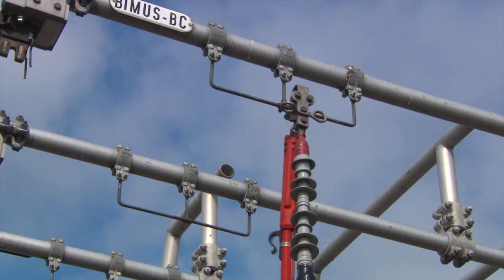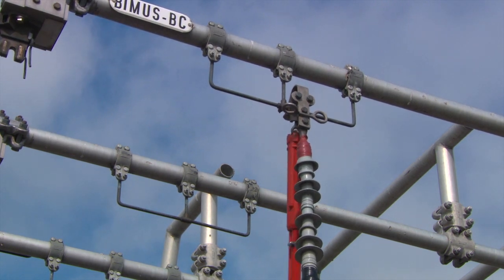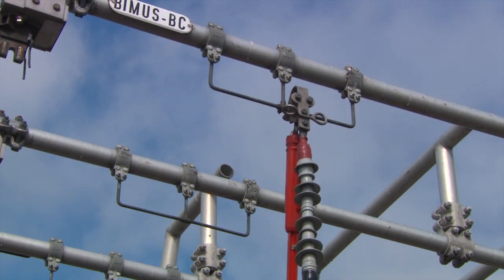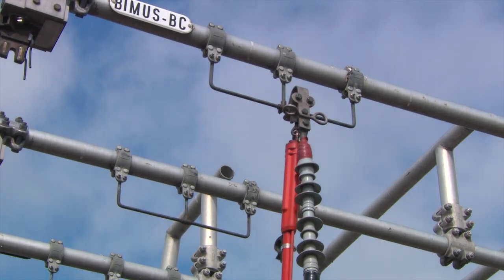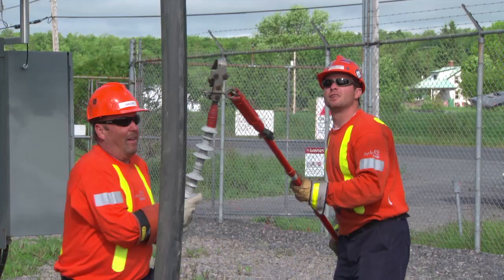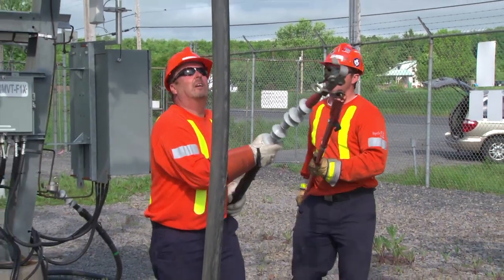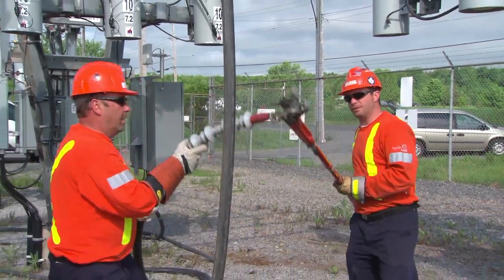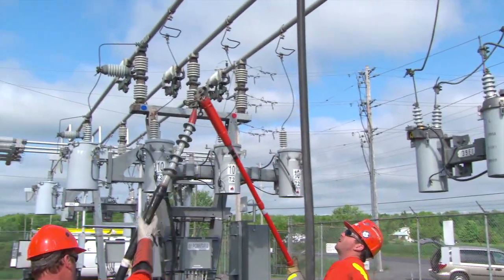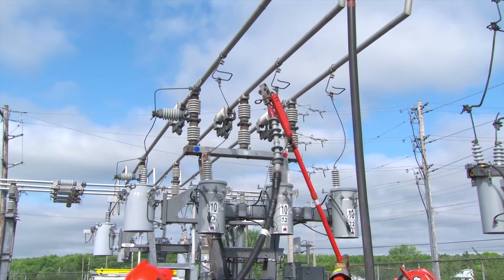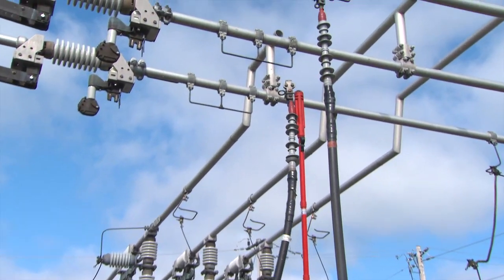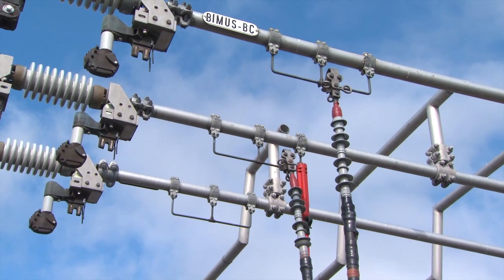The other worker will then release the switch stick hook from the cable connector and attach it to the live line clamp. The clamp is then tightened and checked to ensure it is properly seated and secure. When raising the cable using a switch stick, it's important to use the provided rings and not the live line connector. This is because the weight of the cable could distort the threaded shaft of the connector.